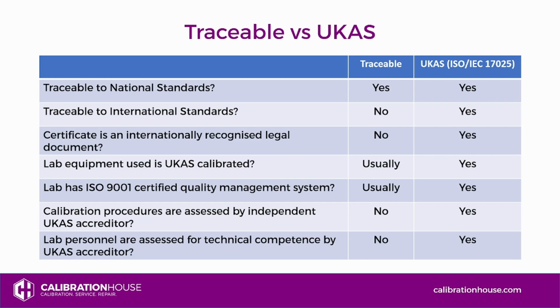Is the lab equipment used to perform the calibration UKAS calibrated? It usually is for traceable, and it definitely is for UKAS. Does the lab performing the calibration have an ISO 9001 certified quality management system? For a traceable calibration, it usually does, but not always. For UKAS, it must. ISO 9001 is a different ISO rule that governs a quality management system of a company.